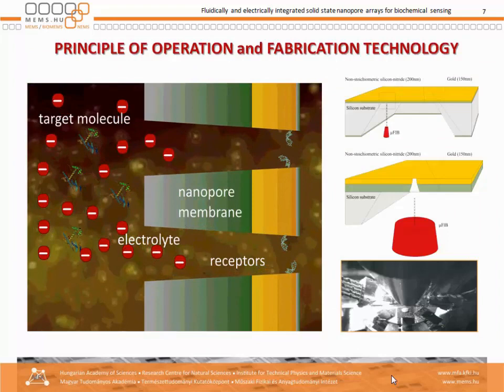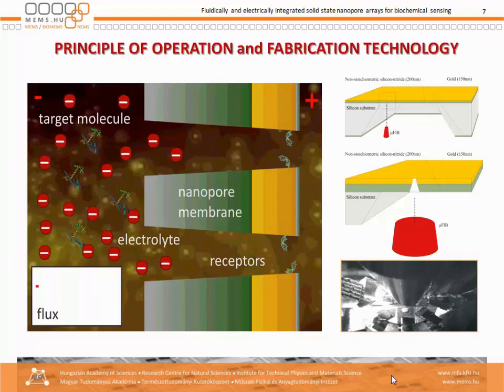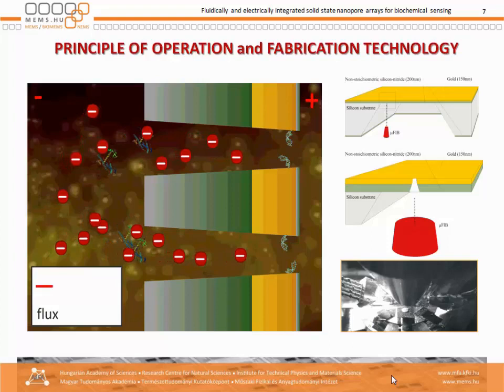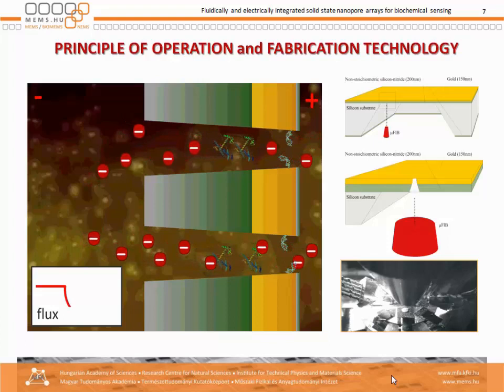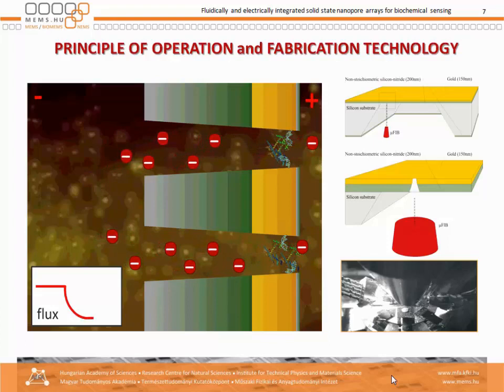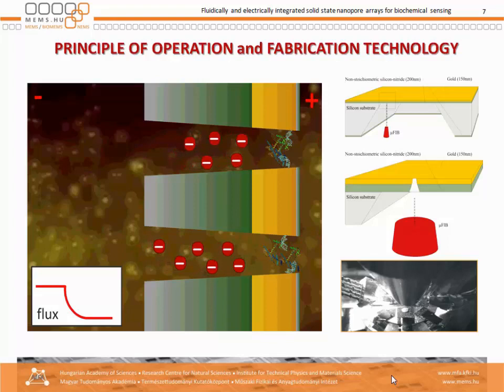Let's look at the sensor technology. The operational principle is shown here in this movie. We have a membrane with nanopores, and the two compartments on both sides of the membrane are separated. The electrolyte from one side containing the specimen flows through the holes, and the specimen can block the conduction of ions through the nanopores, which would be measured as a decrease of conductivity between the two compartments.